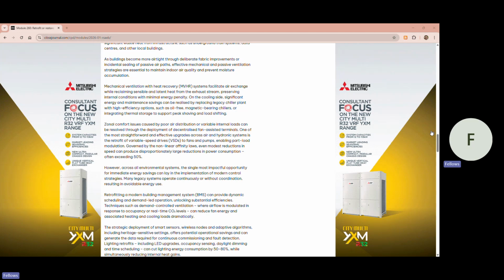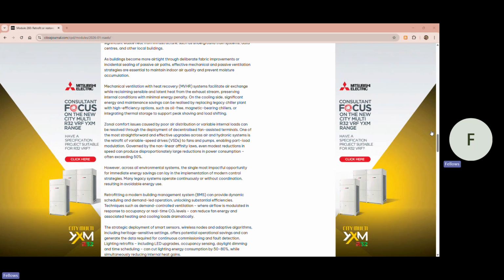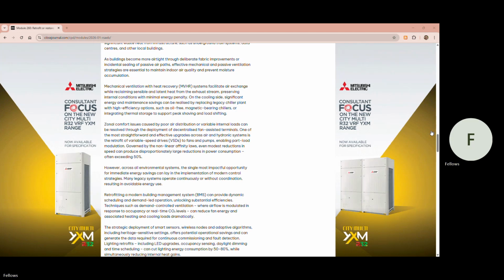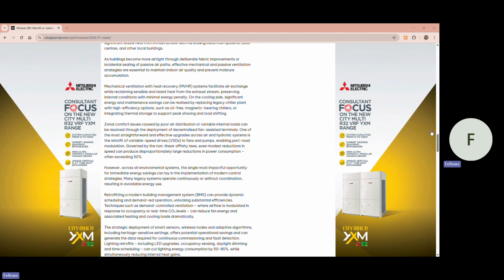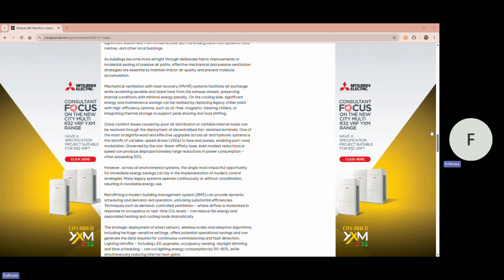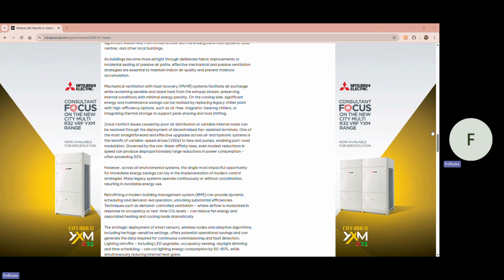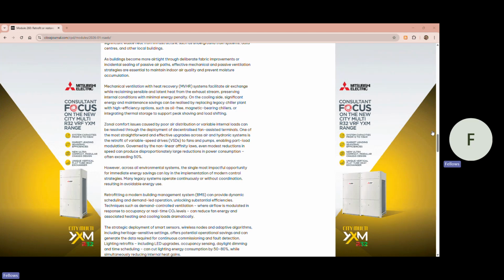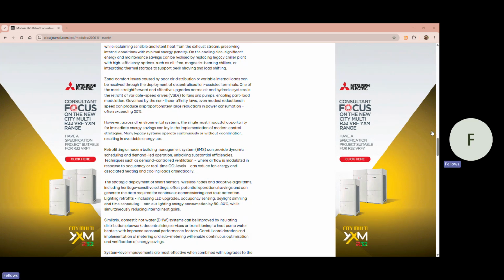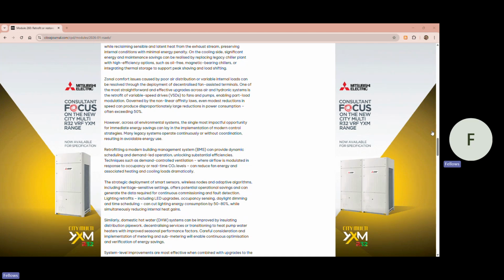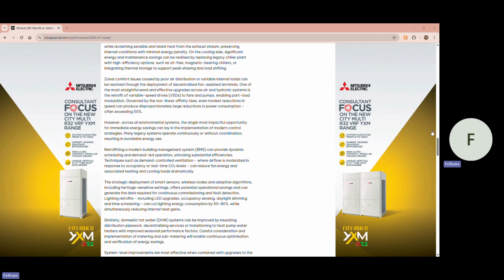Zonal comfort issues caused by poor air distribution or variable internal loads can be resolved through the deployment of decentralized fan-assisted terminals. One of the most straightforward and effective upgrades across air and hydronic systems is the retrofit of variable speed drives, VSDs, to fans and pumps, enabling part load modulation. Governed by the non-linear affinity laws, even modest reductions in speed can produce disproportionately large reductions in power consumption, often exceeding 50%. However, across all environmental systems, the single most impactful opportunity for immediate energy savings can lie in the implementation of modern control strategies.